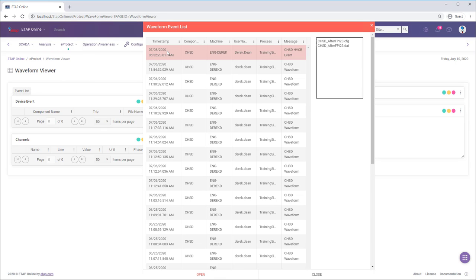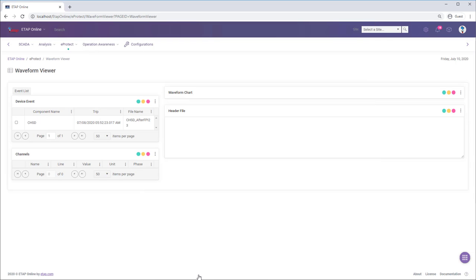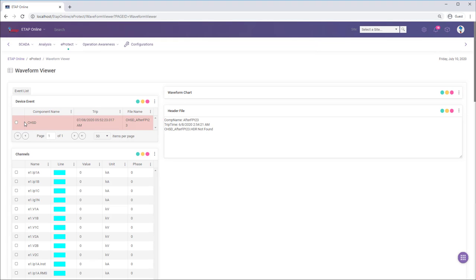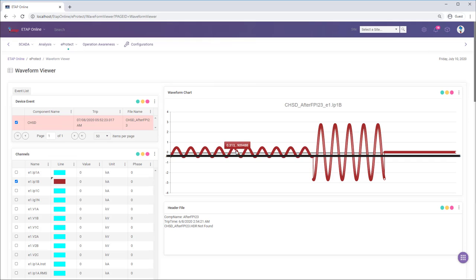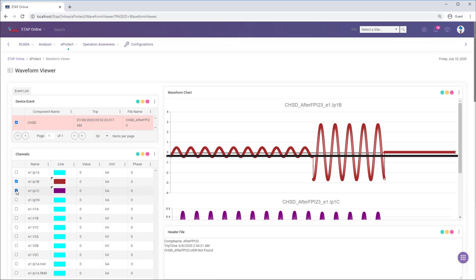Through eProtect, we can visualize any recorded waveform. Selecting the recorded event by component, we can view the details of the measurements captured. All the available measurements that are recorded are filtered under the device. Selecting phase B, current, shows us the captured waveform, and the chart shows the values at any selected point on the plot. You can clearly see the event that occurred and the instantaneous results of that event. Select any measurement you wish to view and a plot will be displayed.